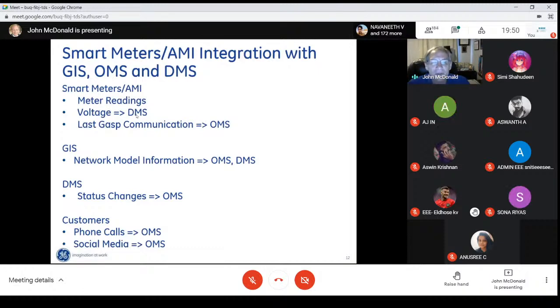I have to make sure that, when I do Volt-VAR control, the voltage at that last customer on the feeder is above 114 volts. Very important. So I ping certain smart meters to get the voltage. And smart meters all have the capability that when they have an outage, there's enough energy in the smart meter for one final communication upstream to the utility, and we put that information in the outage management system. We call that last gasp communication. In other words, your last breath, right before the outage, your last opportunity to communicate.